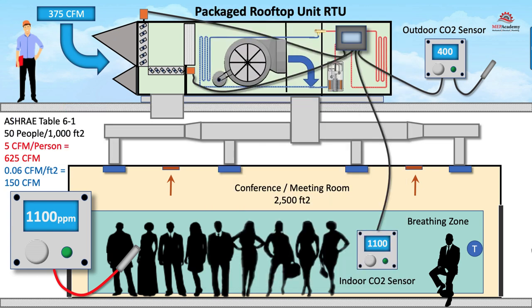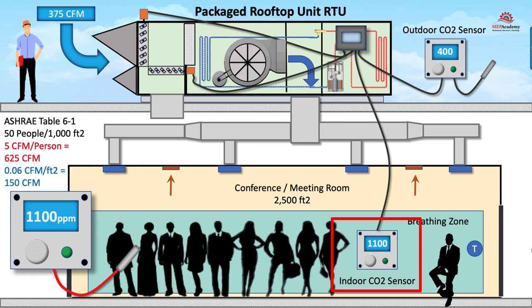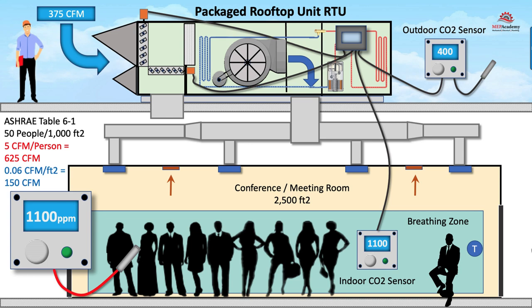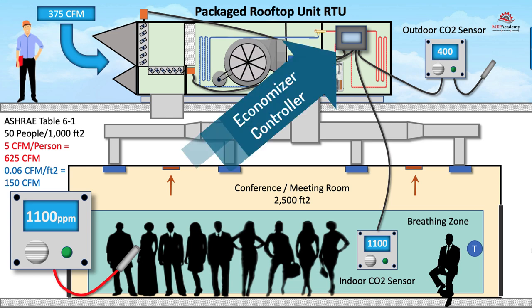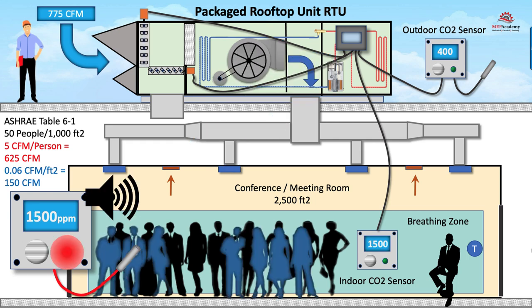CO2 sensors help determine if the current ventilation rate is adequate or if adjustments are necessary. The CO2 sensor provides a control signal based on the measured CO2 concentration. As CO2 levels rise due to occupancy or other factors, the sensor sends a signal to the Building Automation System or the Economizer Control System. When the CO2 concentration surpasses a pre-set threshold, often referred to as the set point, the Economizer Control System increases the outdoor air intake. This adjustment brings in more fresh air from the outside to dilute the CO2 and maintain acceptable indoor air quality. The set point for CO2 concentration can be adjusted based on the specific requirements of the space and occupant density.